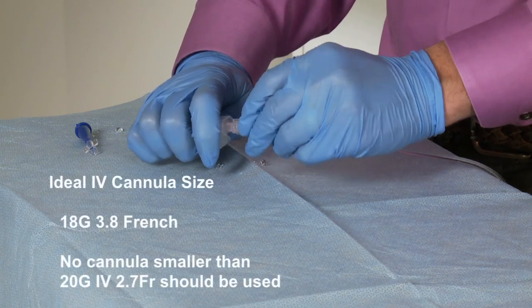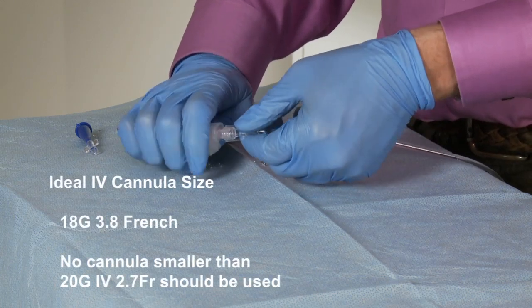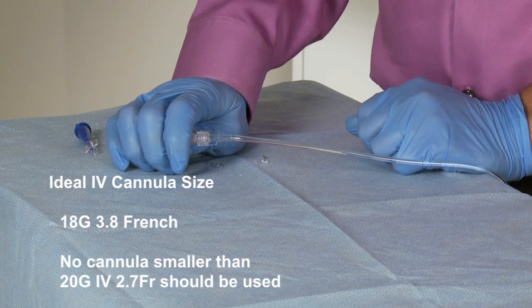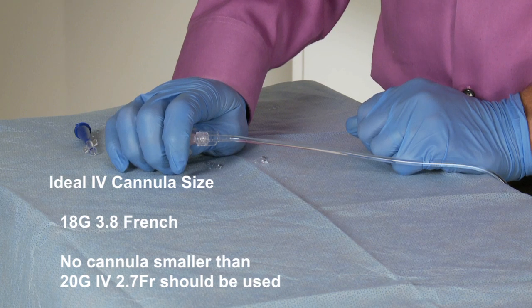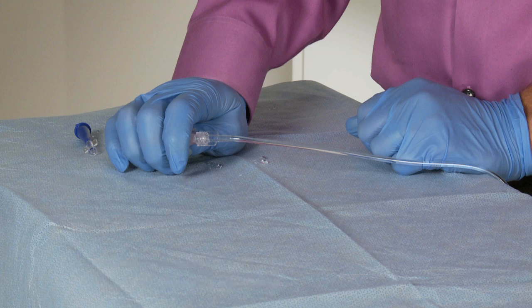Connect the luer connector to the patient's IV. The ideal IV cannula size is 18 gauge, 3.8 French. No cannula smaller than a 20 gauge IV catheter, 2.7 French, should be used. Smaller cannulas will not allow the high flow rates RenalGuard can produce and may result in occlusion alarms.